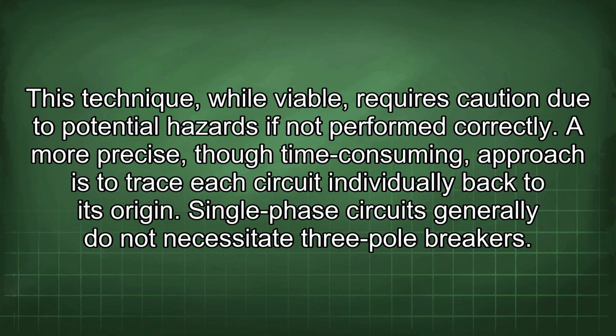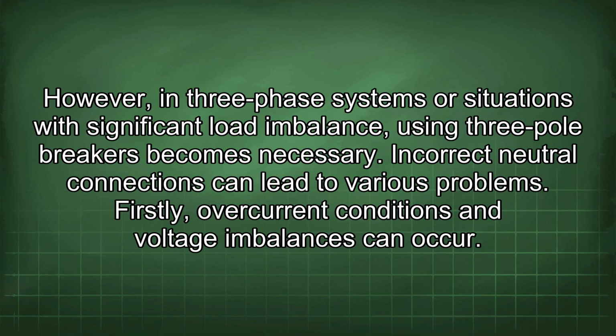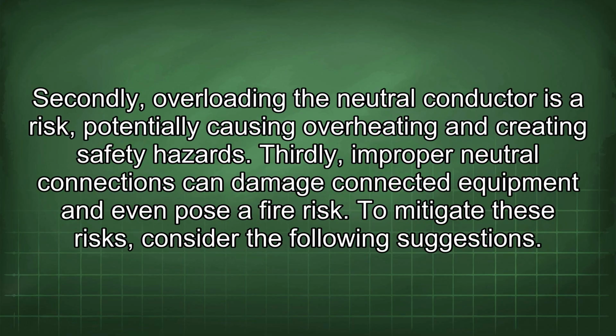Single-phase circuits generally do not necessitate three-pole breakers. However, in three-phase systems or situations with significant load imbalance, using three-pole breakers becomes necessary. Incorrect neutral connections can lead to various problems. Firstly, overcurrent conditions and voltage imbalances can occur. Secondly, overloading the neutral conductor is a risk, potentially causing overheating and creating safety hazards. Thirdly, improper neutral connections can damage connected equipment and even pose a fire risk.